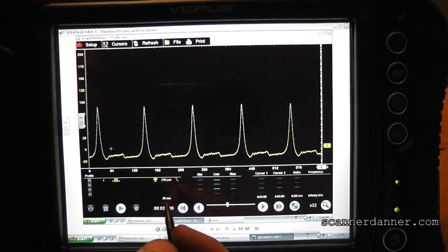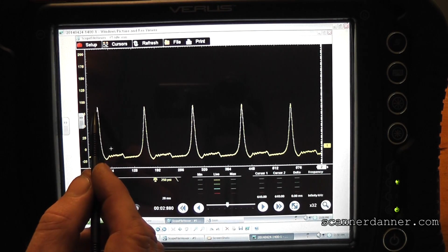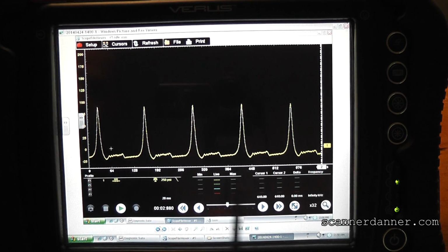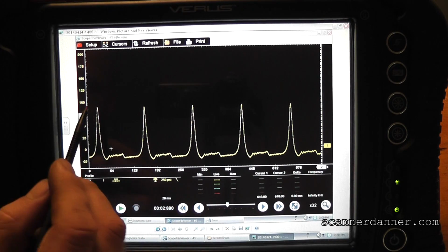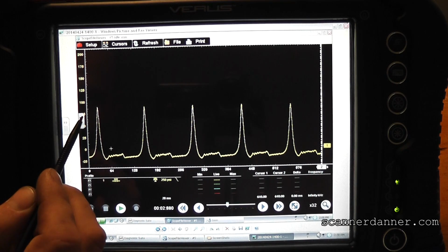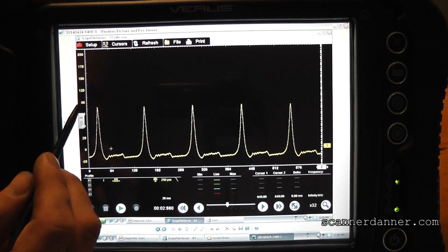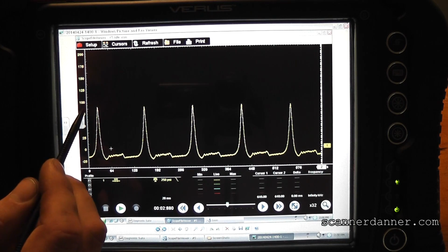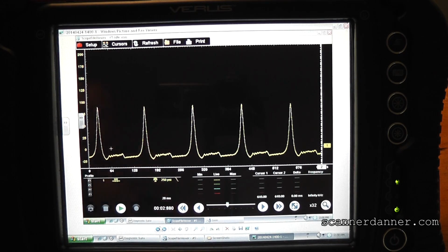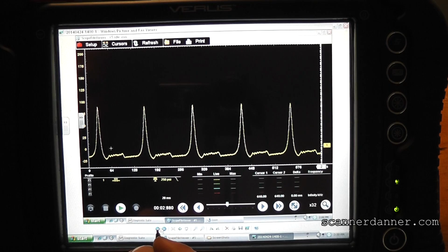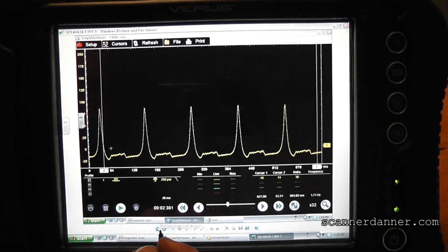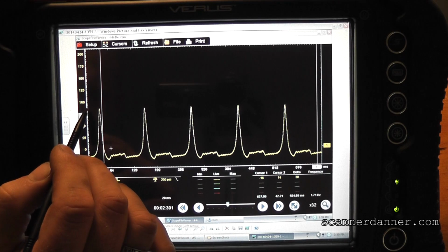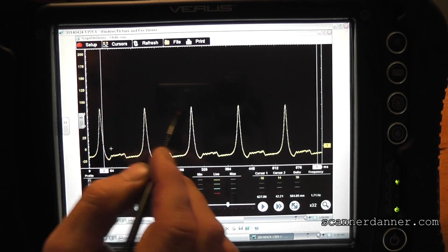Now, somebody else that maybe knows a little bit more about these can chime in and say, hey, look at this part of the waveform, you can see such and such. But the peaks of these compression towers, I don't have my numbers in here, and this is a frozen picture, but let me take a look, that's 50, that's 75, this is 100, so in between 75 and 100, just above, maybe about 80 or 90 PSI, I think is what I remember measuring before. This is the number 5. And my number 4 is really close to that too. It's about the same, about 89 to 90 PSI at the top.